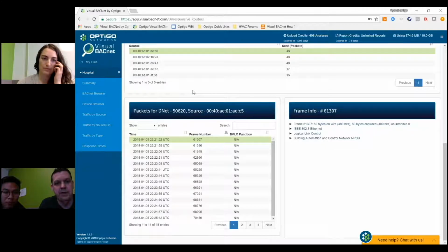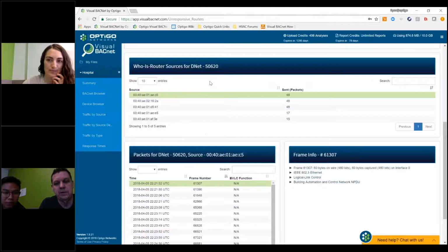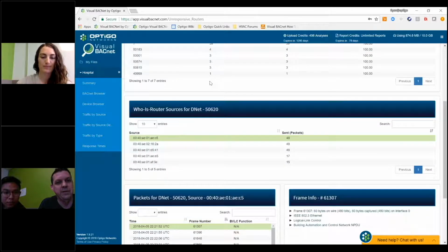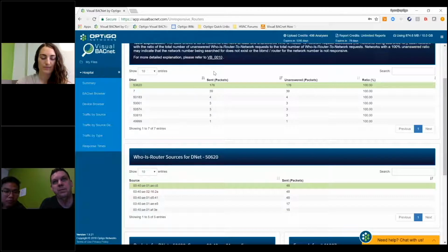So now you can dig into those controllers, look at where all the data transfer is, and see why this network keeps coming up. Unfortunately, the way it is in the world is, as we decommission different controllers in different areas of the building, then things get missed, and that's just the nature of the beast. But it does add unnecessary traffic to your network, and the longer that building's around, the more of this you have, and the more plugged up with stuff it gets.